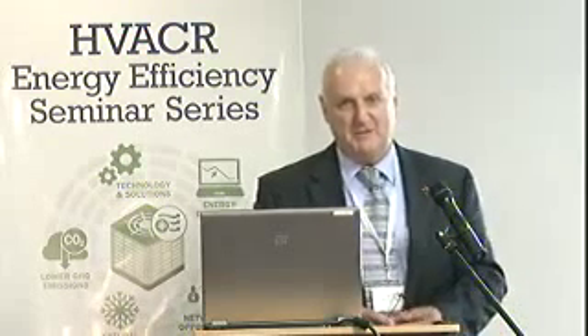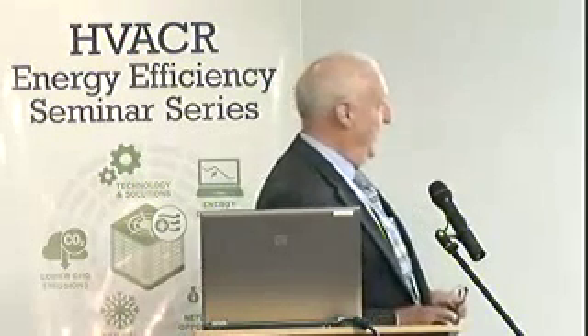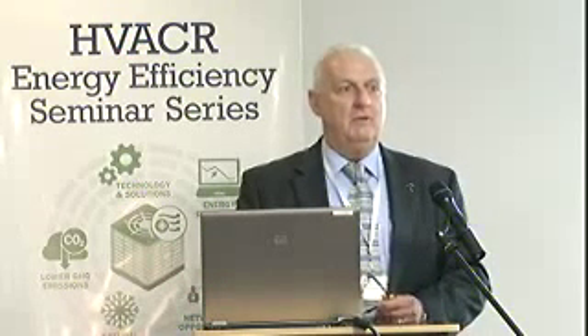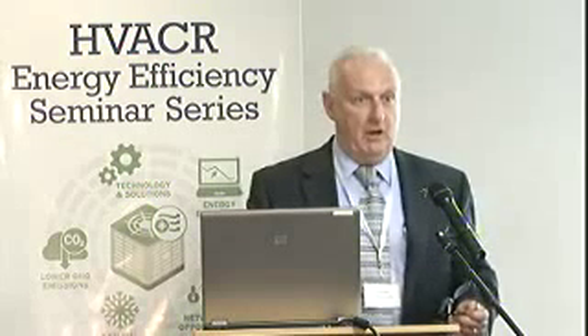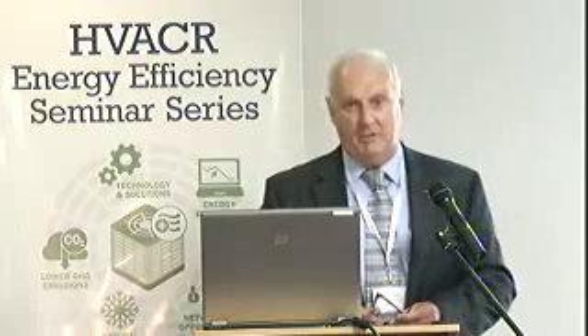So let's get into what really matters, not me telling you about me and the company. Some common beliefs, and effectively this is a shopping list of the things I'm going to talk about. These are the things that people have some misconception about in the marketplace: that the supply voltage is 240 volts, and if it's not 240 volts, there's a problem. I've had electricians contact me to say, it's 220 volts, there's a major problem here, when that was actually the design voltage. That it's constant, that the three-phase supply is a balanced supply. It's not always. Motors are designed for optimum performance at 240 volts. Reducing below 240 volts will increase the current and burn out my motors. So we're going to address all of these issues, and rather than keep reading them, I'll move on because I know time is short.